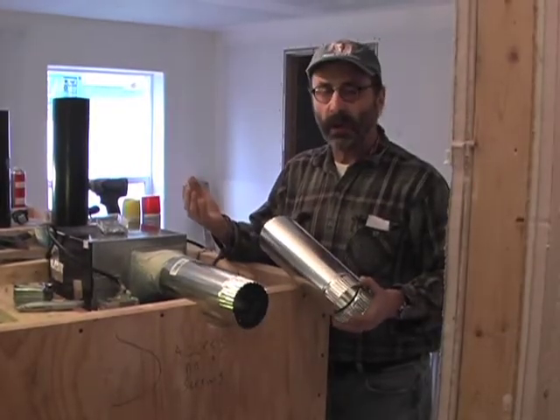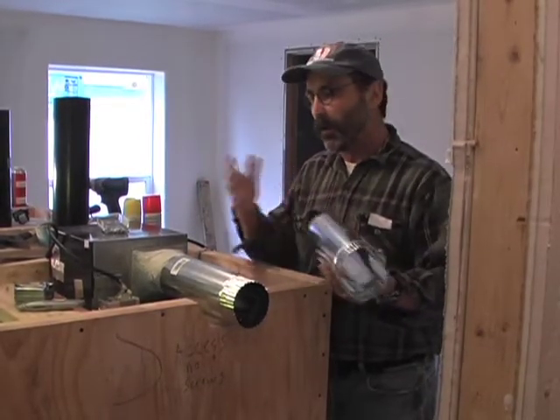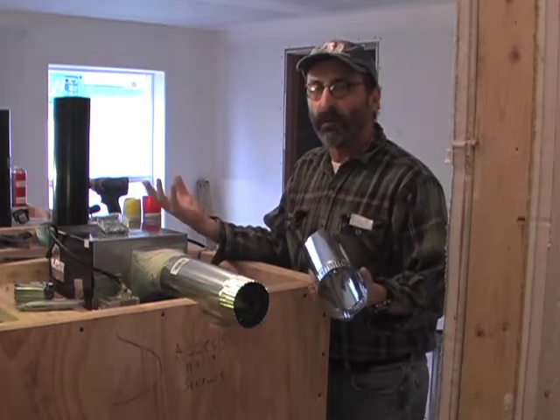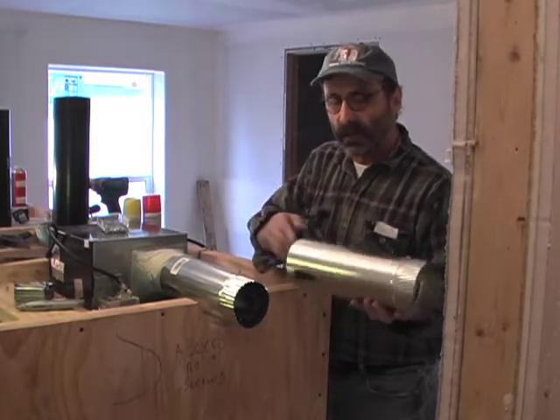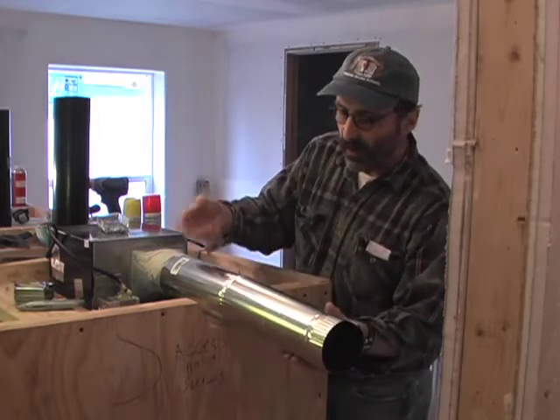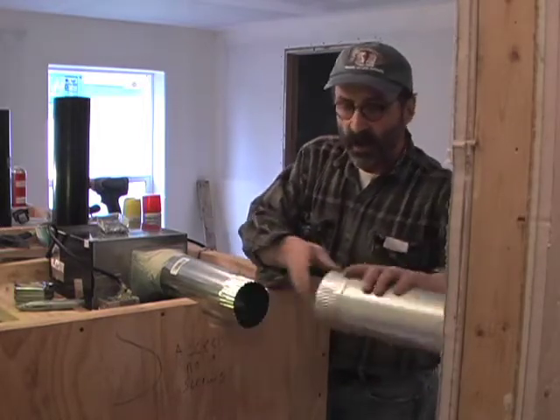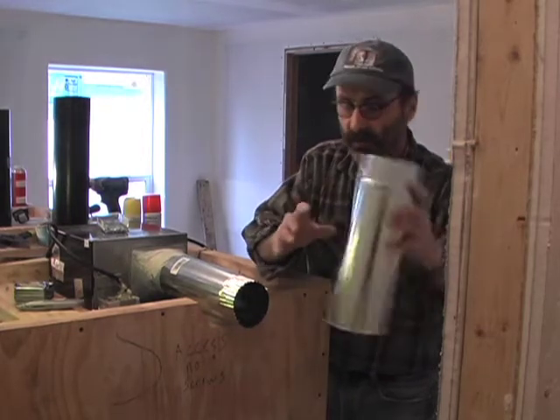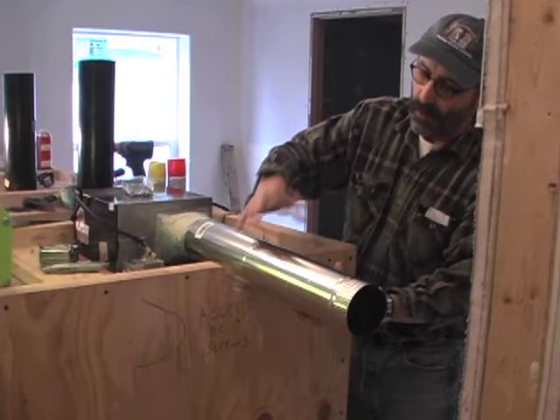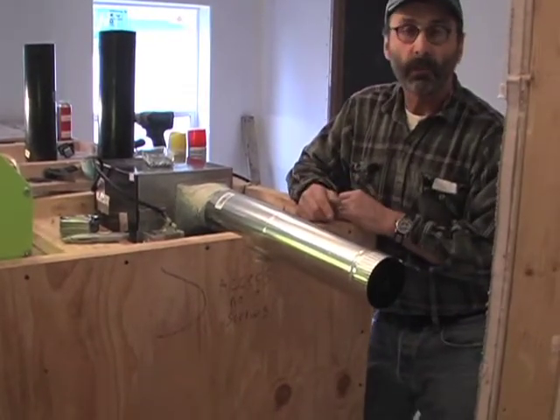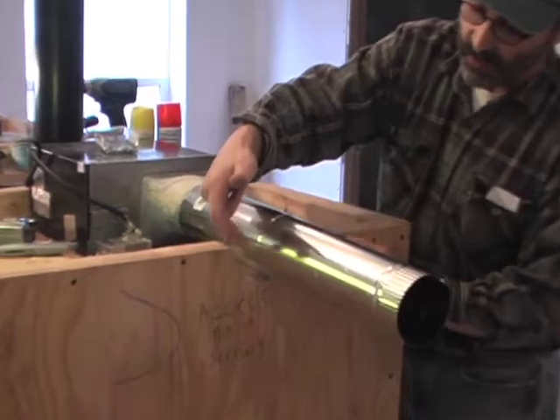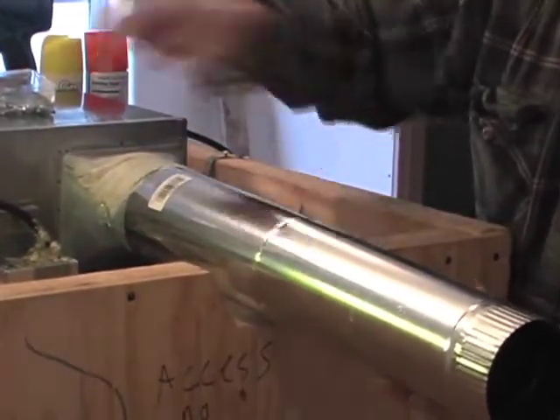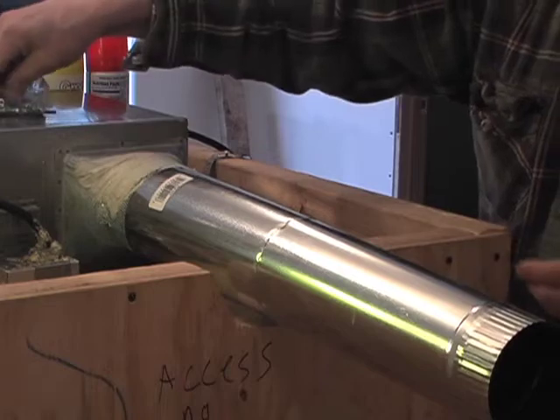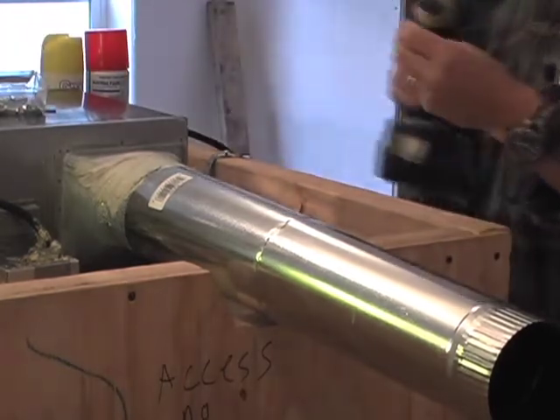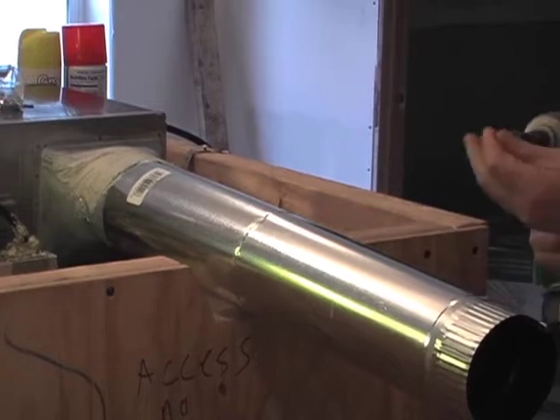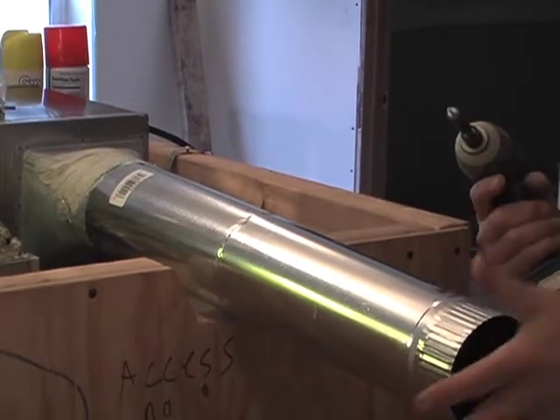Remember, as you start orienting your ductwork, you don't want to create resistance. In this case, we're pulling moisture and air out of a wet room and ducting it to the outside. So we want to make sure our fittings go male into female, and not something that's going to create more resistance. Code requires 3 fasteners per connection. I would say 5 o'clock, 7 o'clock, and 12 o'clock would be good choices, again keeping the fasteners out of the bottom of the ductwork. Keep an eye out so that you don't create a kink in here.